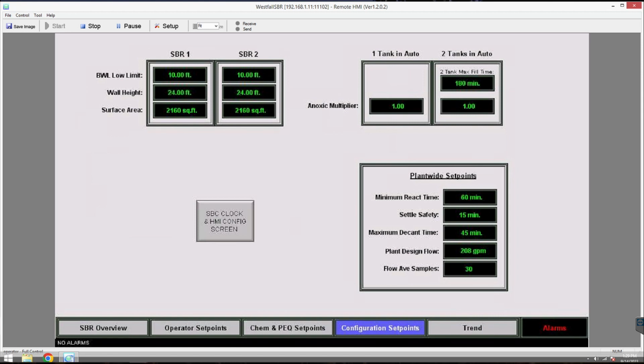Yeah. So we changed the way the set point is named, but it works the same. We just call it something different, rather than saying, tell us how tall your wall is, and then we'll just assume that we can go 1 foot below that. We thought that was confusing, and so we said, no. Nowadays, we just call it software ETWL, and you set it exactly where the highest point is that you want to be able to fill that tank.